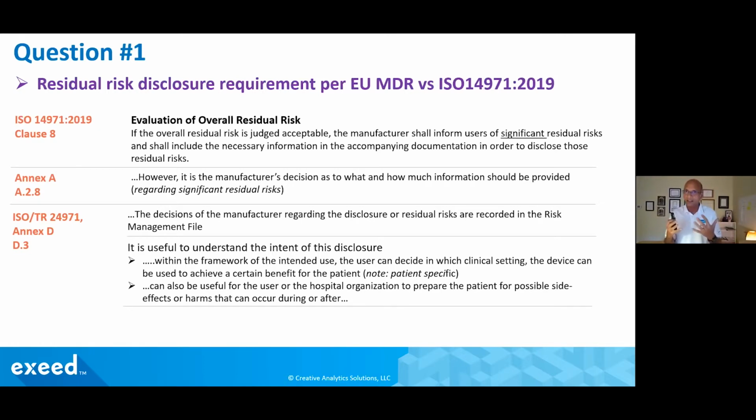Let's understand the context and the intent. Further, it can also be useful for the user or the hospital organization to prepare the patient for possible side effects or harms that can occur during or after the use of the device. That's another purpose. We need to know the residual risks to be able to inform and prepare the patient.